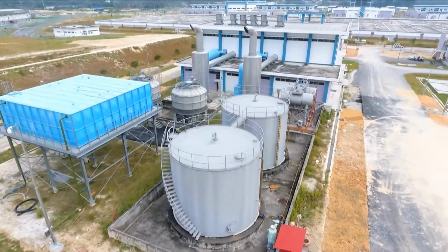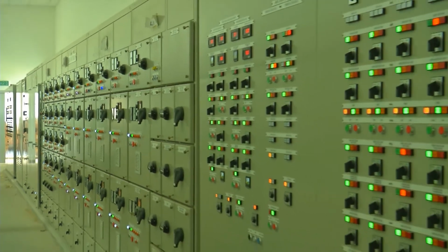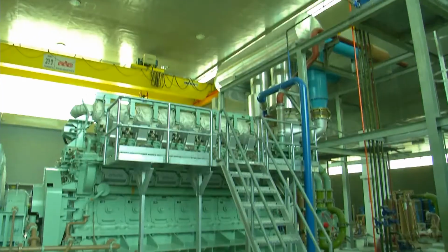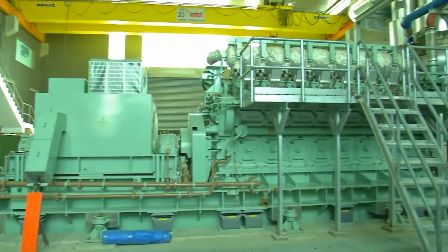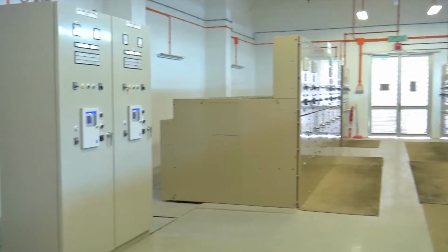Generating plant. An alternative power source is provided via backup diesel engine-driven generator sets, 2 numbers of 6.6 kV, rated at 5.5 MW, with a synchronizing switchboard located at the generator building.